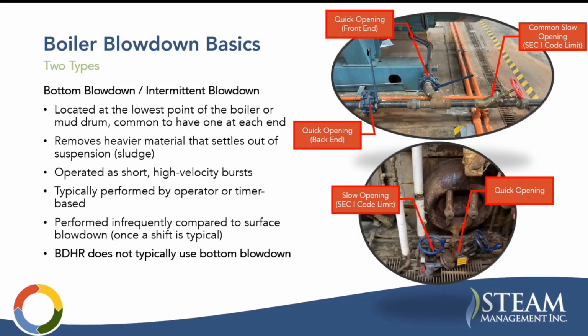And then this bottom picture here, this is the mud drum of a water tube boiler. So same idea, you have your quick opening and your slow opening. Then I should point out the second valve is your Section 1 code limit on most boilers. And that will be important later when we talk about different configurations. Again, this is not the subject of this presentation as far as a heat recovery opportunity, but it's important to know.